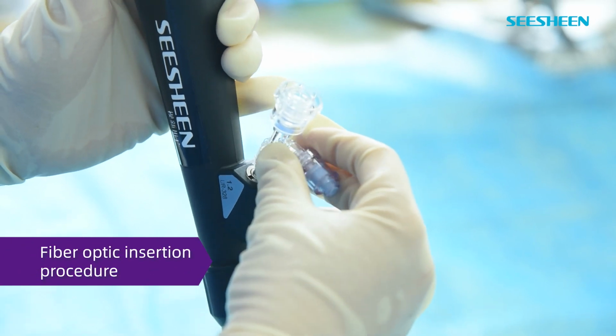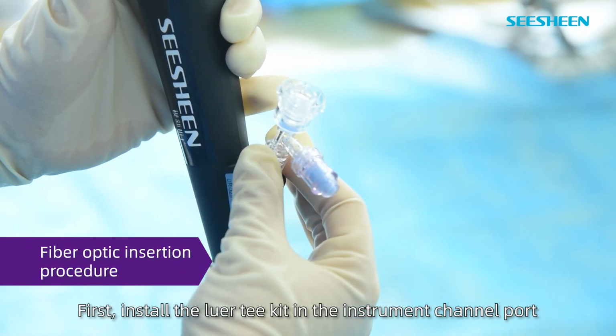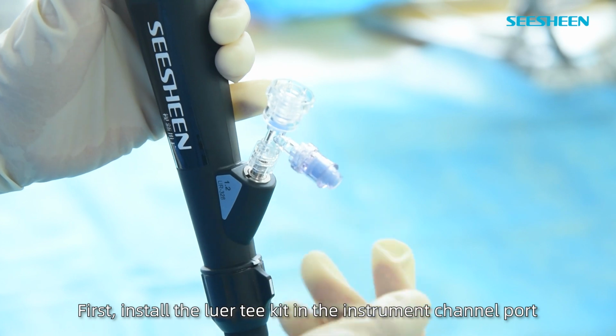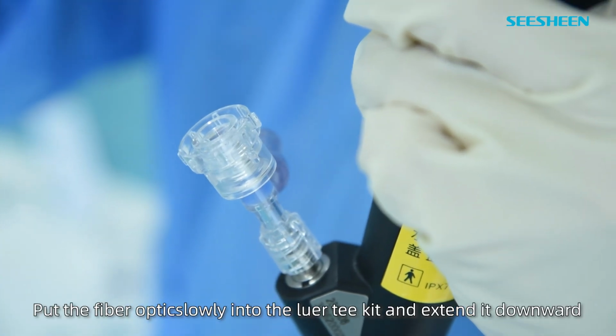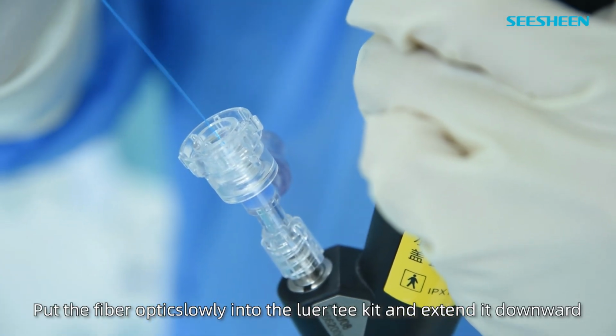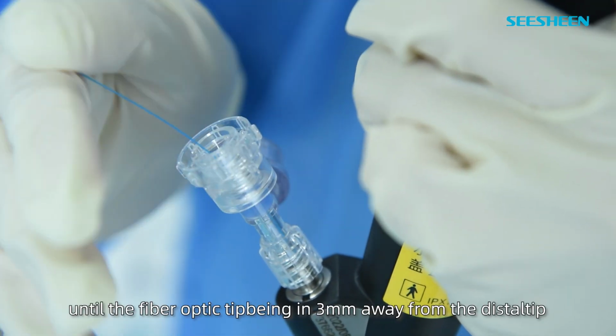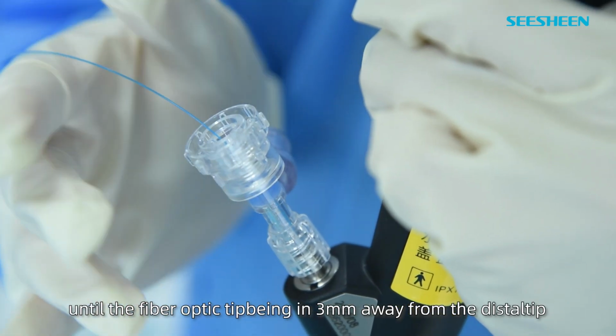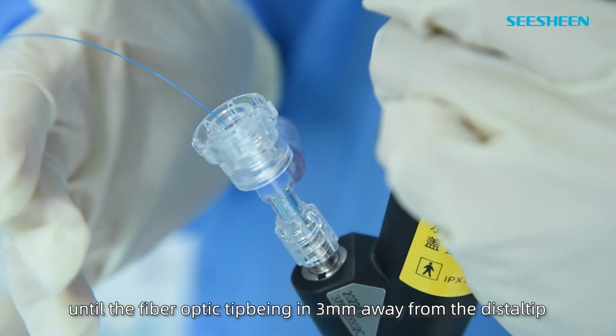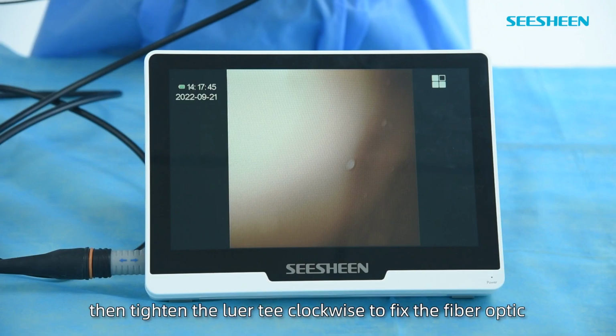Fiber optic insertion procedure. First, install the Luer T-kit in the instrument channel port. Put the fiber optic slowly into the Luer T-kit and extend it downward until the fiber optic tip is 3 mm away from the distal tip. Then tighten the Luer T clockwise to fix the fiber optic.